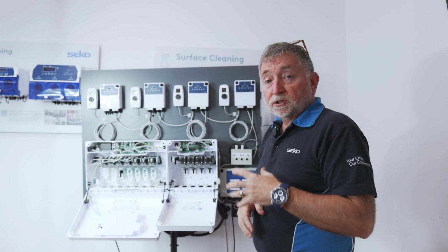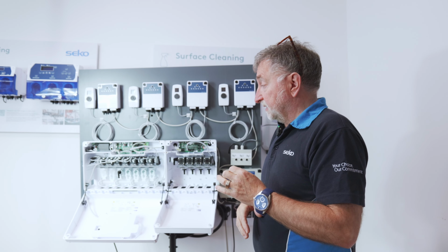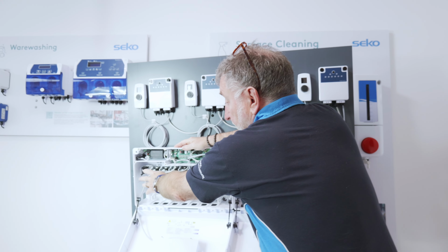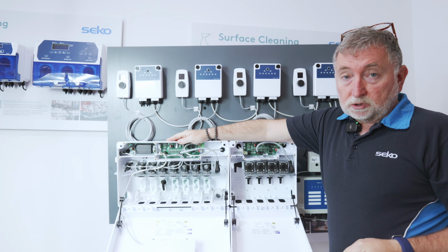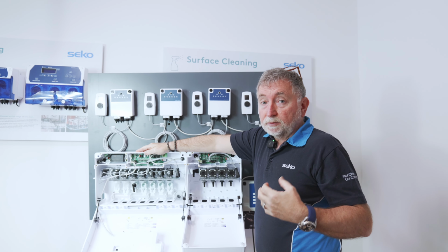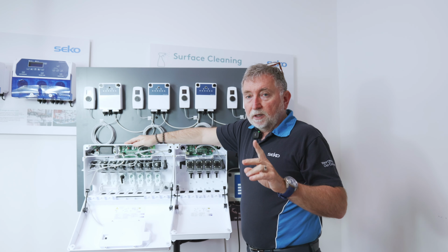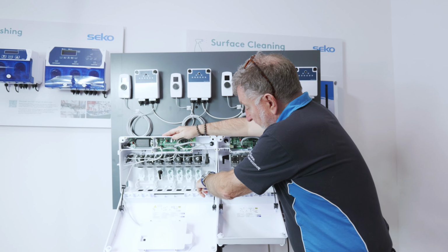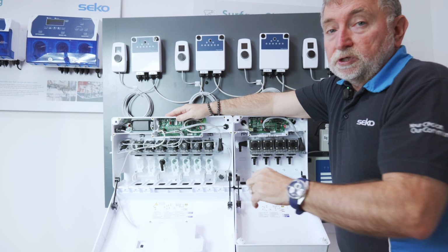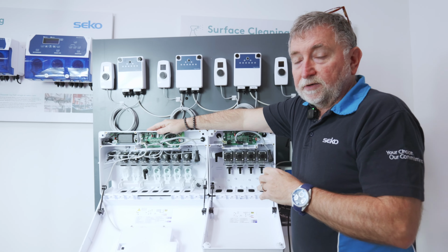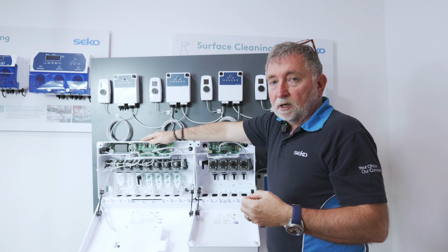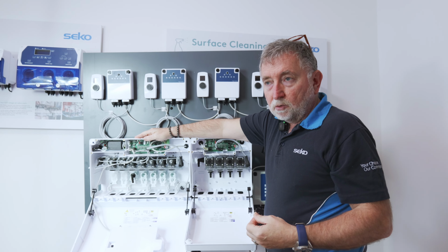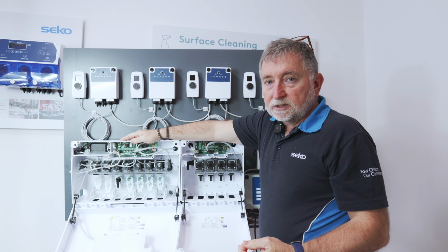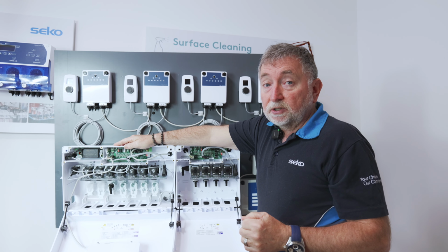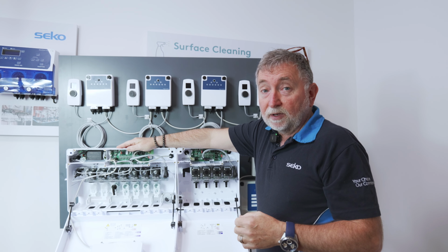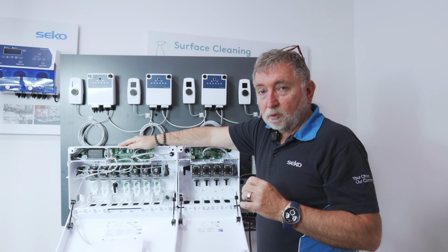One of the key features on the LS100 is the flow meter. The standard unit is fitted with 1 flow meter which measures the incoming water. So if there's any problems with the water supply, then you'll be issued with an alarm. As an optional extra, we can have a secondary flow meter on the unit which measures the chemical and water leaving the unit. So it can give you the additional alarms that if there's any problems with the supply of chemical, if there's reduced flow rates, and it also negates the need to calibrate the unit because it's measuring the chemical as it leaves the unit. People find that quite a useful function.